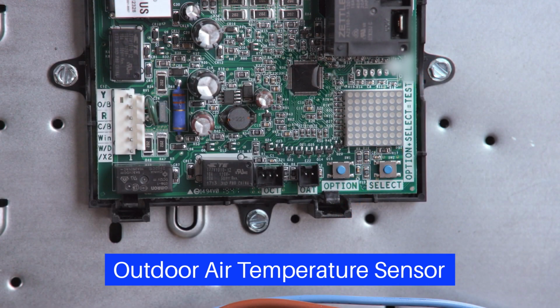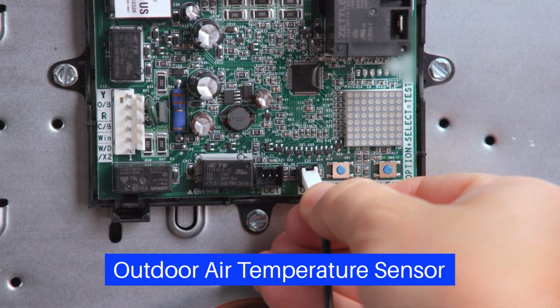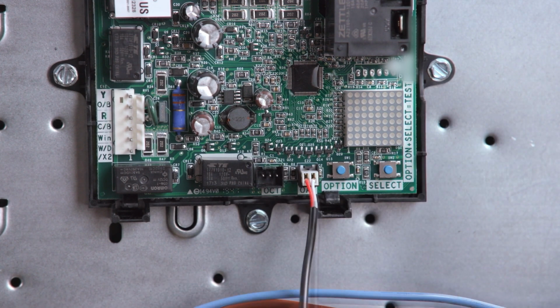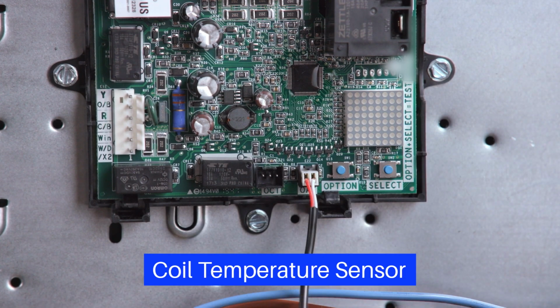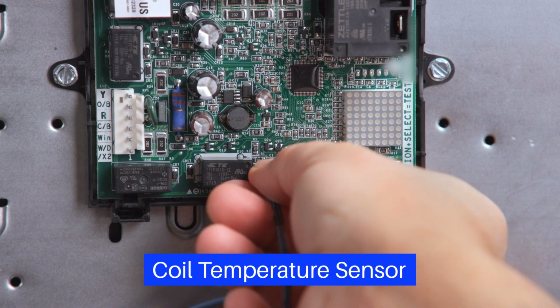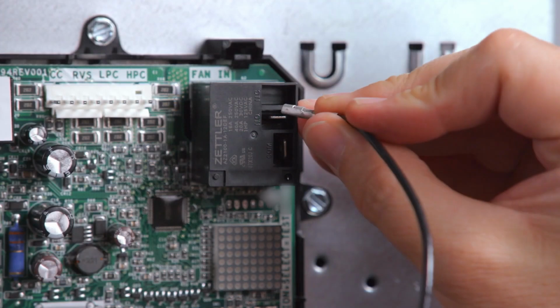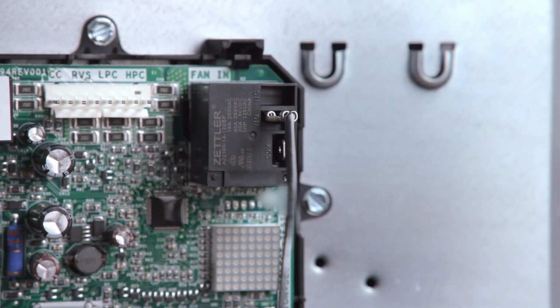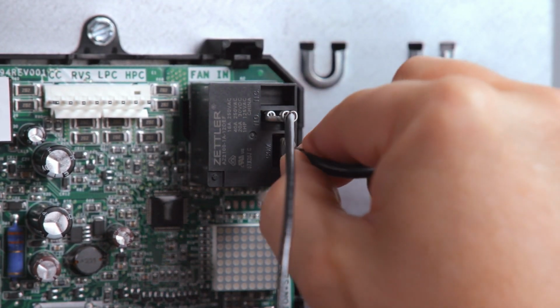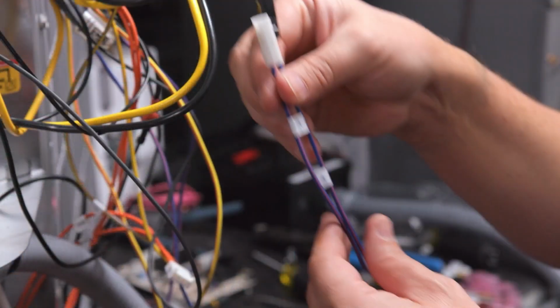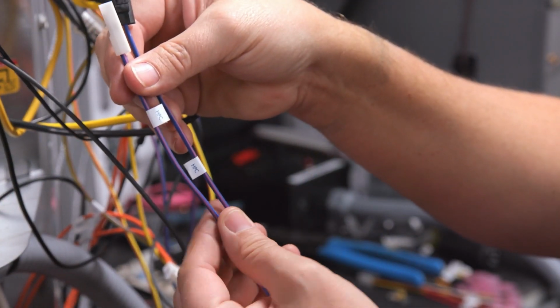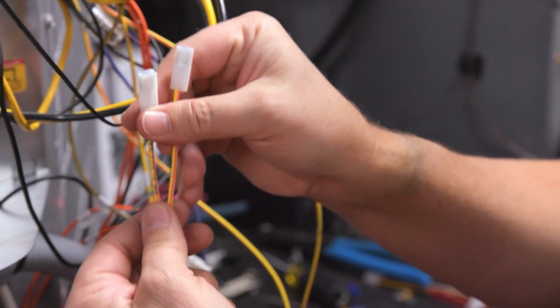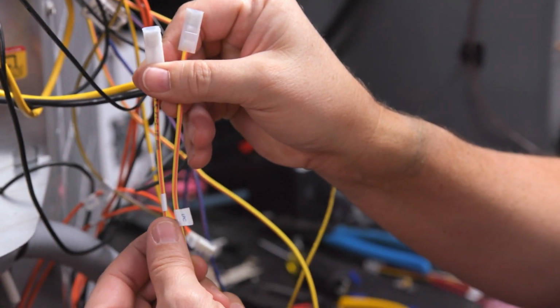Plug the sensor into the 2-pin OAT connector on the defrost control. Plug the coil temperature sensor into the 3-pin OCT connector on the control. Connect the condenser fan motor wires to the fan in and fan out terminals. For this application, the high pressure switch uses a blue wire with a pink stripe, and the low pressure switch uses a yellow wire with a pink stripe.